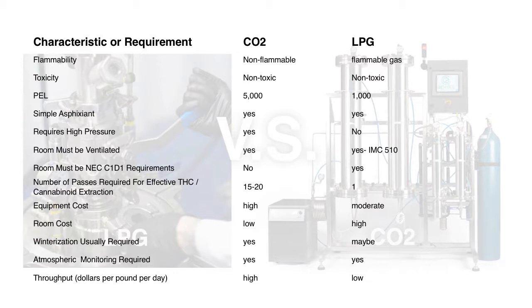As far as the pressure, for CO2 we need a minimum of 900 psi, and most of the time, bottom line, you never operate less than approximately 1,200 psi, and many machines operate up to 5,000 psi. So we have equipment that has high pressure, and high pressure engenders other hazards. Obviously, if things break, they're like projectiles, like a bullet firing. LPG usually operates from about 25 to 125 psi, so it's much lower pressure.